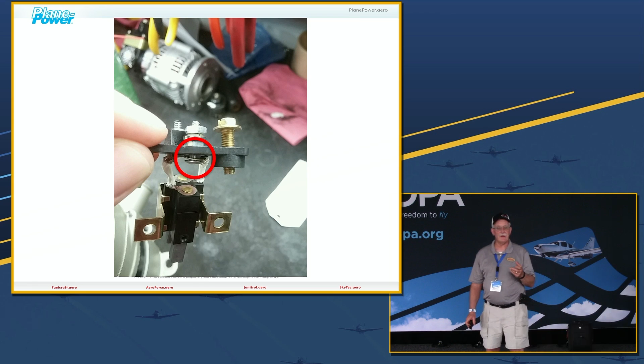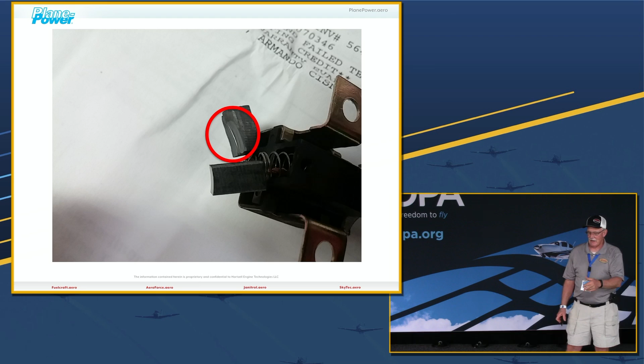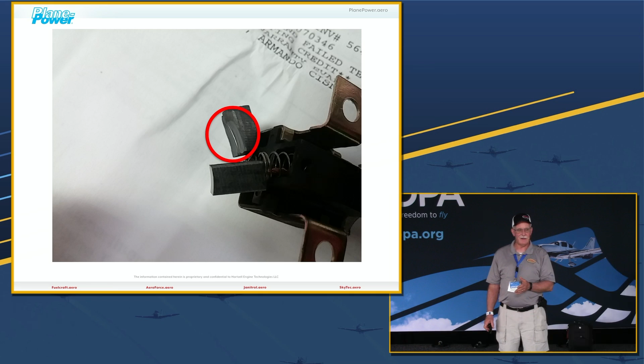Probably more intermittent than working, actually. There's a brush that got put back in wrong, so instead of running on the face, it somehow got back in there on the side, and when it did that, it shorted against the shunt wire coming through. But it actually worked for a while. It's like, wow.